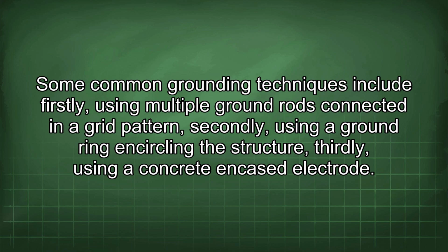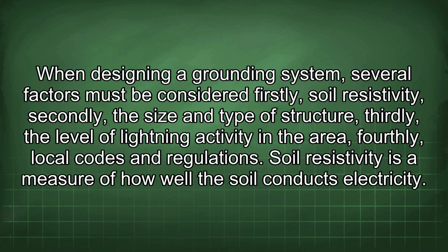Some common grounding techniques include, firstly, using multiple ground rods connected in a grid pattern; secondly, using a ground ring encircling the structure; thirdly, using a concrete encased electrode. When designing a grounding system, several factors must be considered. Firstly, soil resistivity; secondly, the size and type of structure; thirdly, the level of lightning activity in the area; fourthly, local codes and regulations. Soil resistivity is a measure of how well the soil conducts electricity.